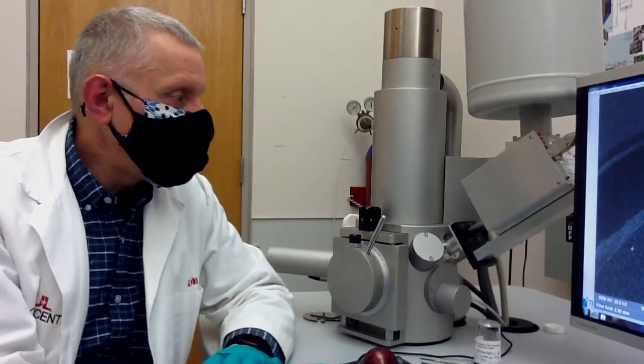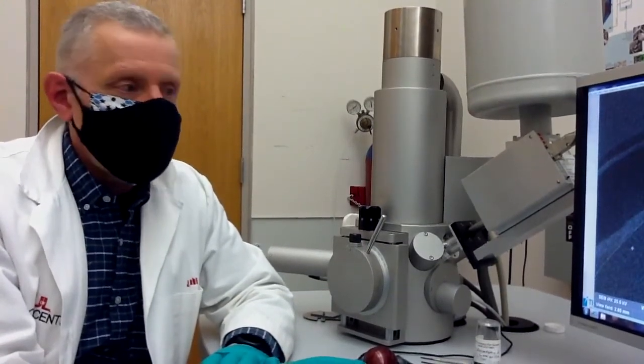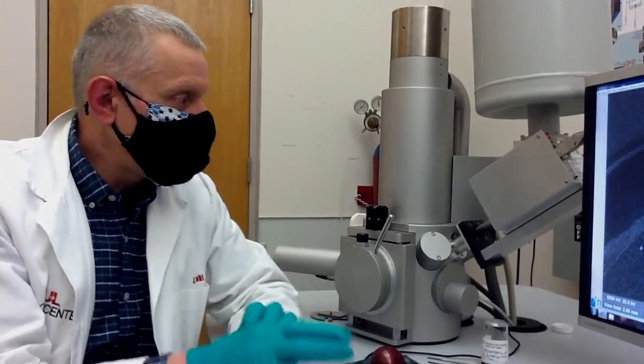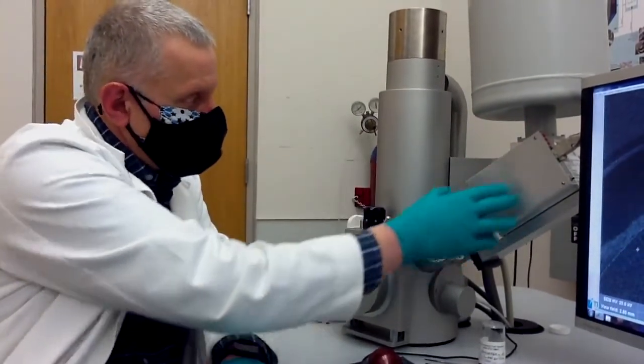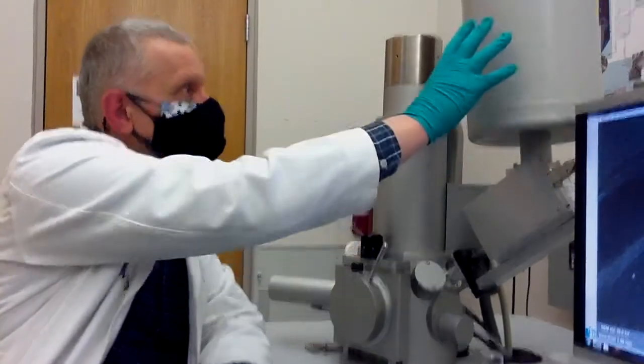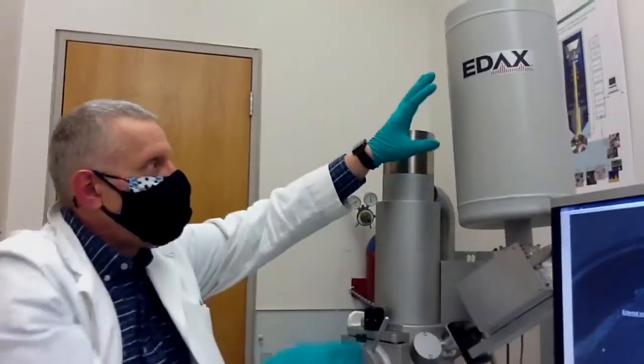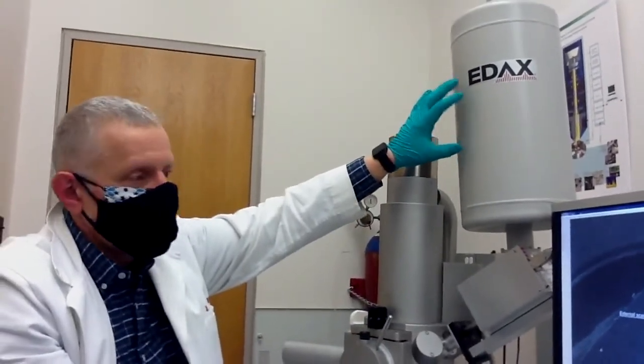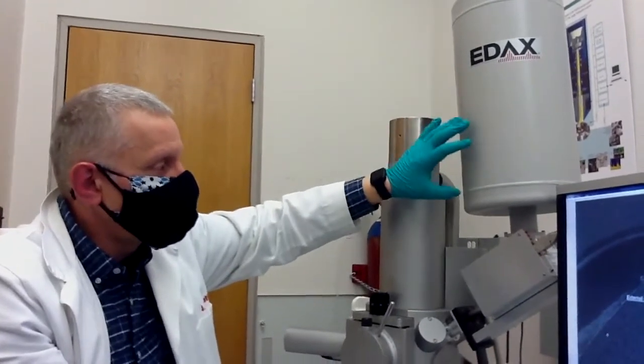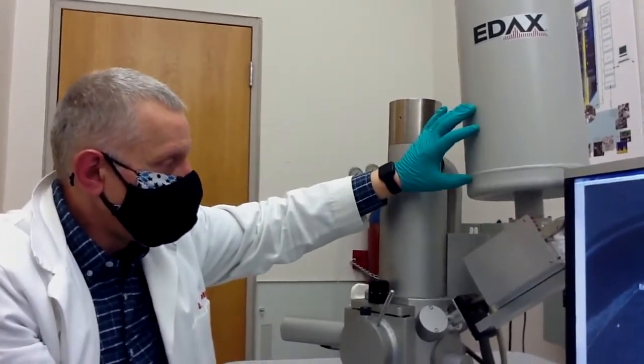For the elemental analysis or chemical analysis using the EDS technique, we will use the EDS detector, which is basically this component here. It has this big reservoir where we have to have liquid nitrogen just to cool it. The detector needs to be cold to operate.